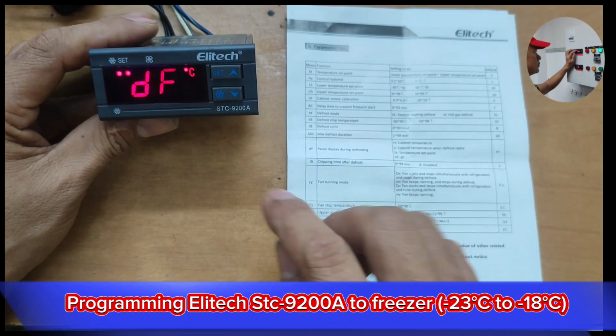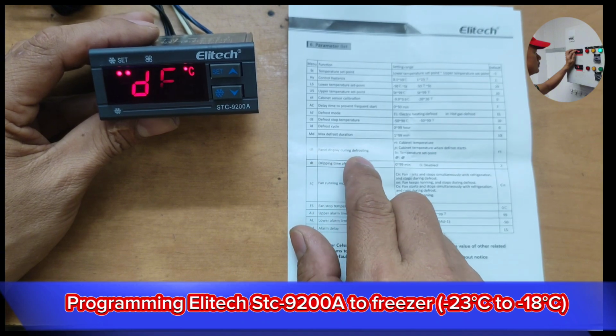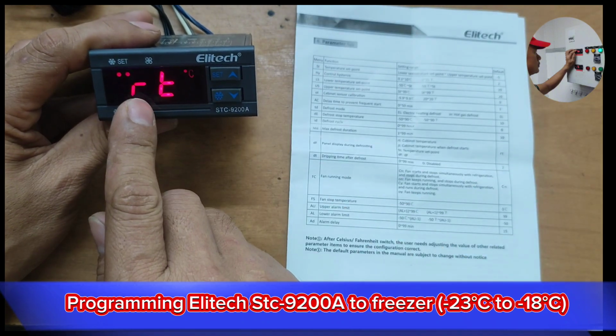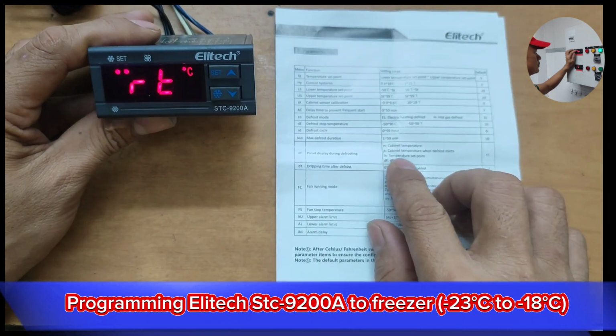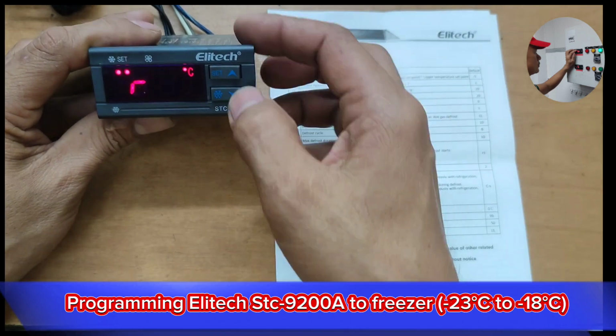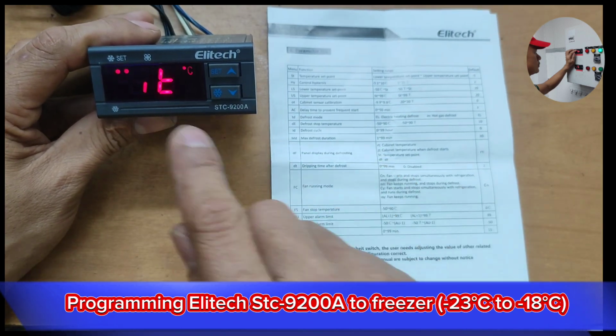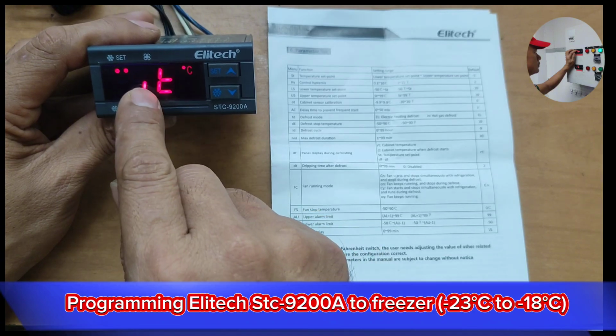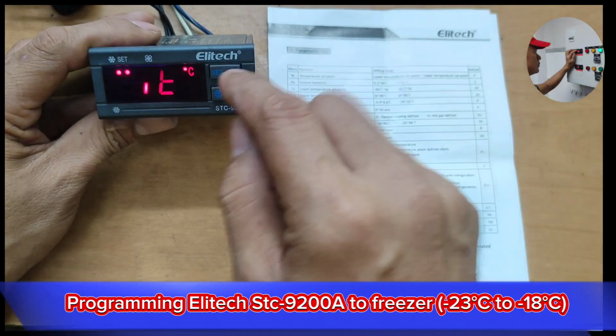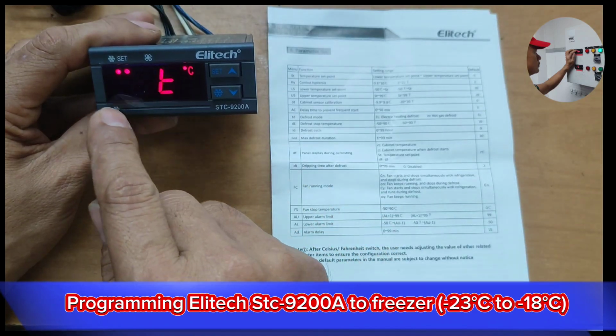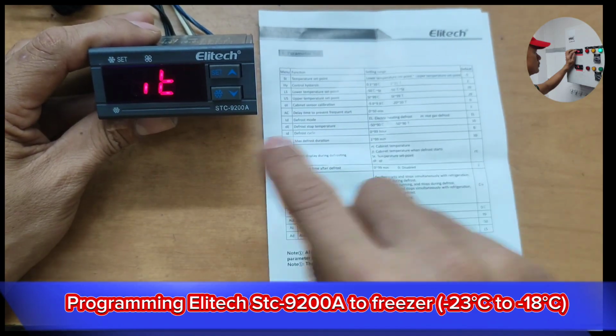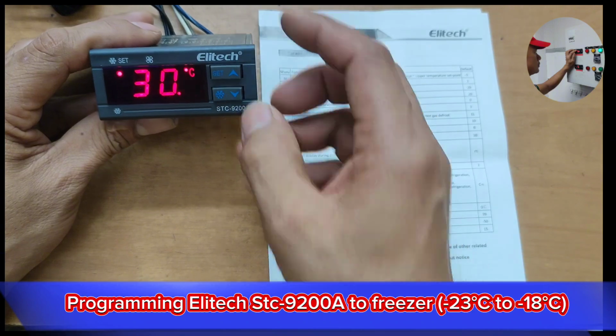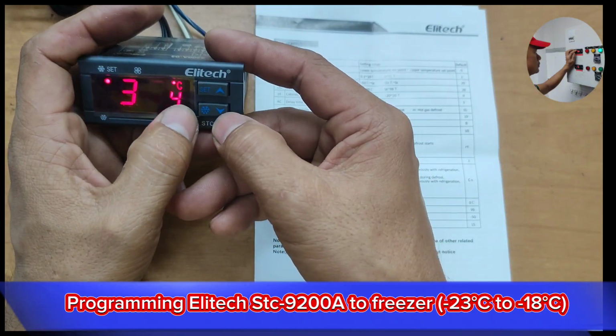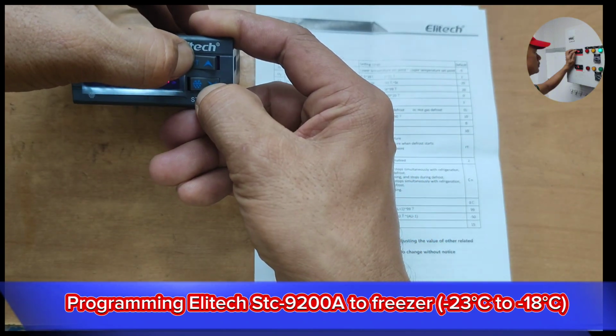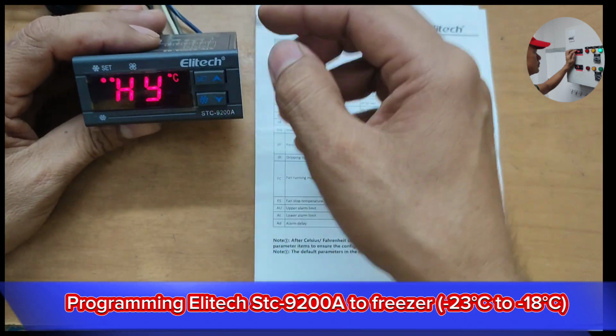Then preset. And DF, panel display during defrost. From here, if we choose RT, the cabinet temperature will show. If you choose IT, the cabinet temperature when defrost started will show. For example, the defrost happens at negative 18, and until the end of the 20 minutes of defrost, what shows is negative 18. And after 15 seconds of inactivity, we're going to lose the program.